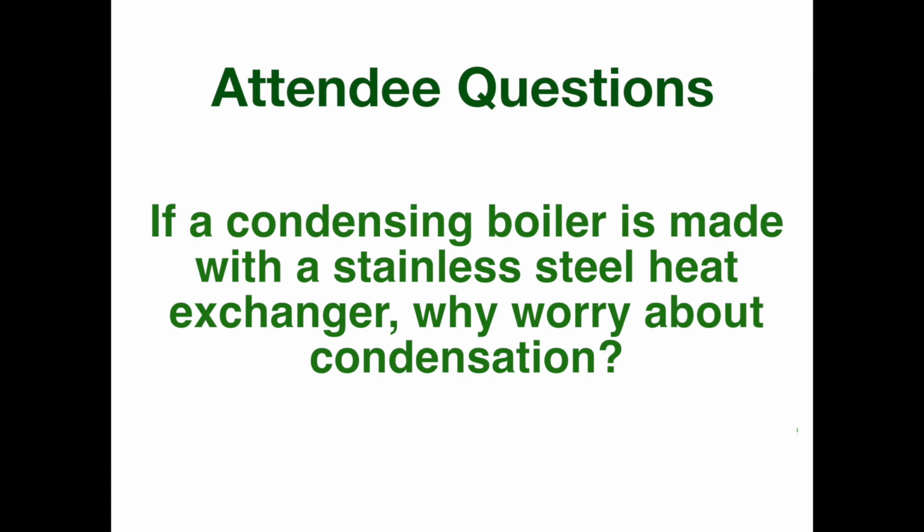Most boilers, especially the biomass boilers today, do need some type of external boiler protection, either a loading unit, a high flow capacity mixing valve, or sometimes a three-way motorized valve with boiler return temperature sensing.